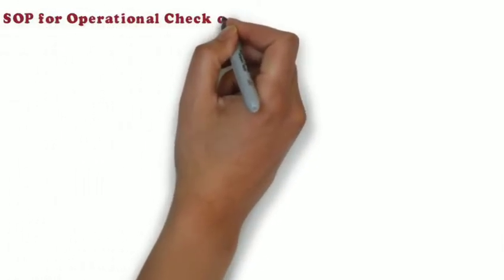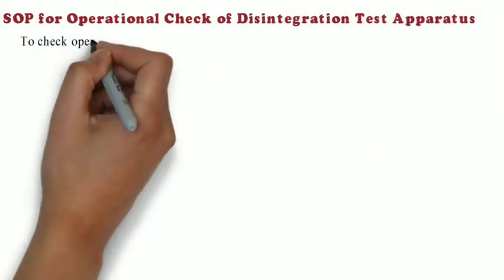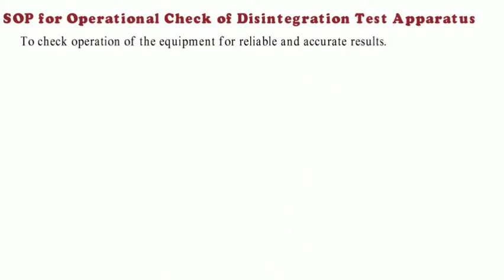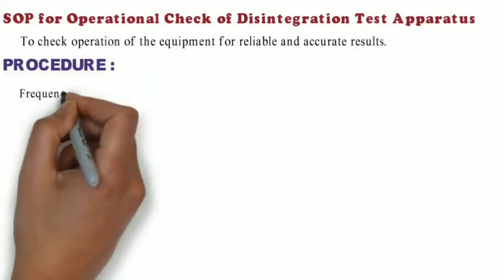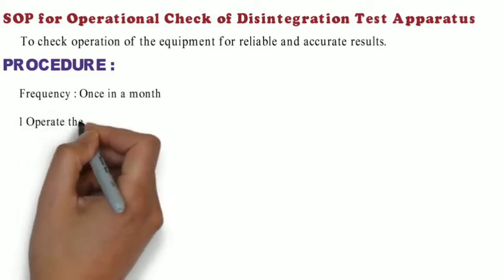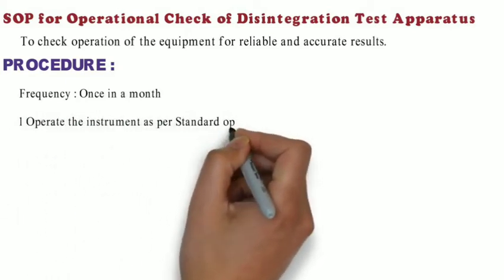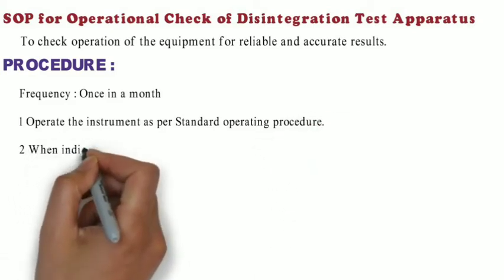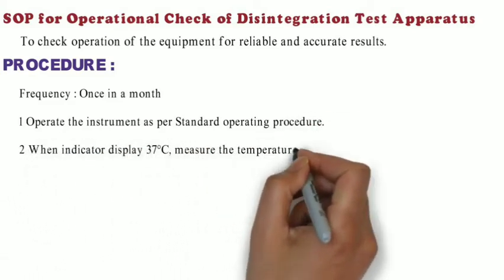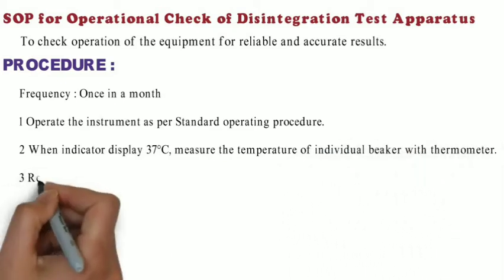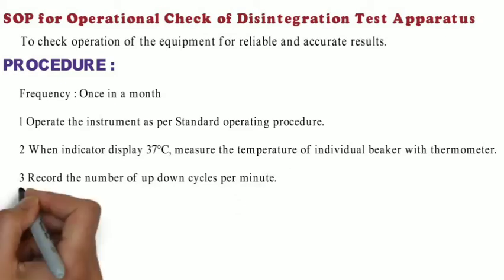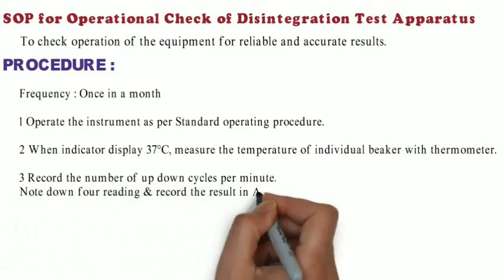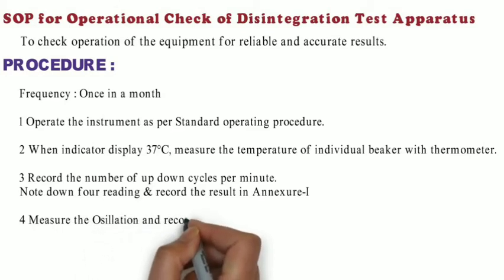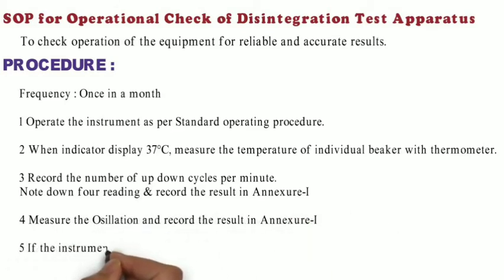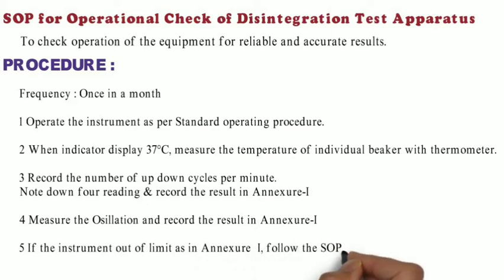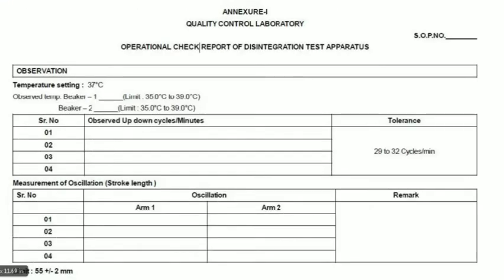Then the SOP for operational check of the disintegration test apparatus, to check operation of the equipment for reliable and accurate results. Frequency: once in a month. Operate the instrument as per the standard operating procedure. When the indicator displays 37 degrees Celsius, measure the temperature of the individual beakers with a thermometer. Record the number of up-down cycles per minute, note down 4 readings and record the results in Annexure 1. Measure the oscillation and record the results in Annexure 1. If the instrument is out of the limit given in Annexure 1, follow the SOP.